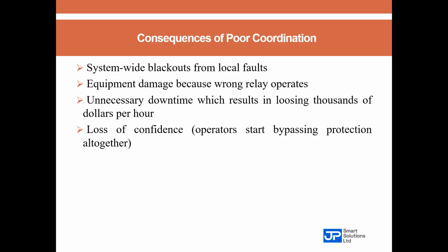Now, let me give you a famous case. A refinery suffered a total shutdown due to a 0.4 kV fault, a fault on their 0.4 kV bus bar. But the main 11 kV breaker tripped before the feeder breaker. So production losses ran into millions, unnecessary downtime. And all this is because someone skipped proper coordination.